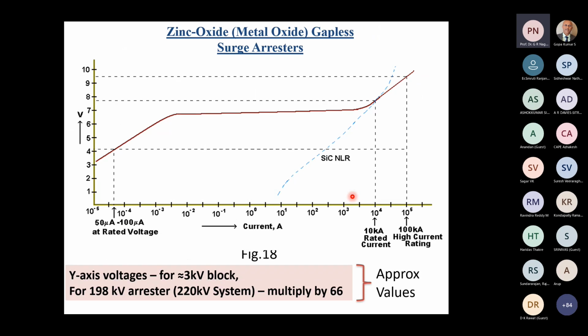Now, how to suppress that? How can you think of, for example, an 800 kV line starting with a 2.5 megavolt impulse? We provide lightning arresters which have non-linear resistors inside. So when the voltage exceeds a certain level, the current starts flowing through the arrestor. Once the current flows through the arrestor, it develops a certain voltage. The non-linear resistor has very, very non-linear resistance. As the current increases, the voltage does not increase substantially. It remains almost constant in the case of what we call metal oxide resistors or zinc oxide arrestors.